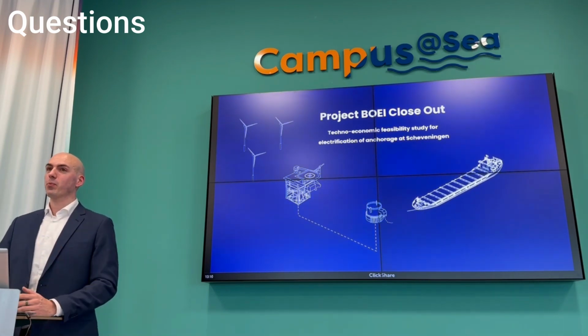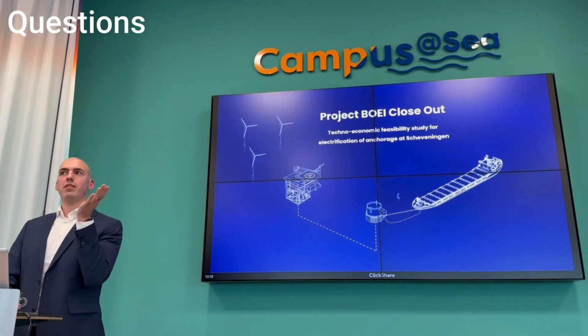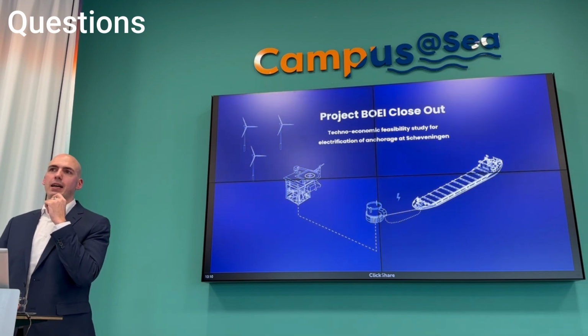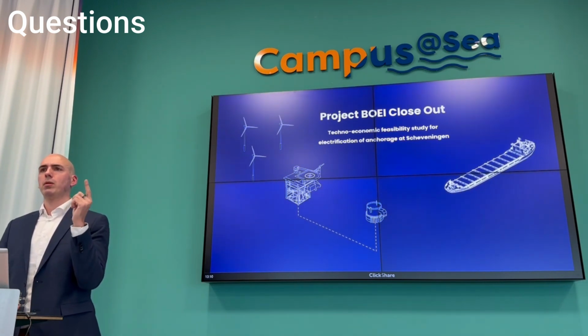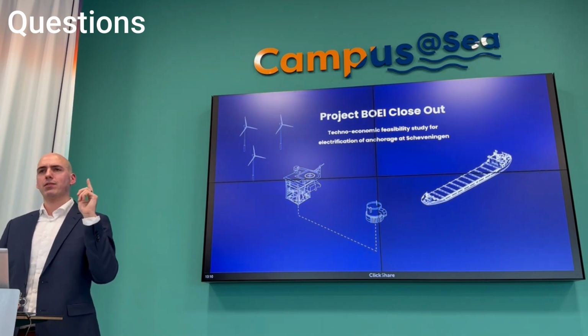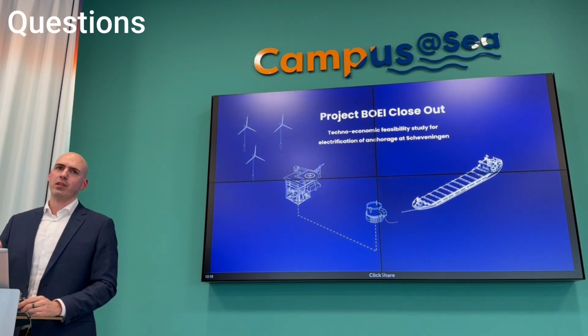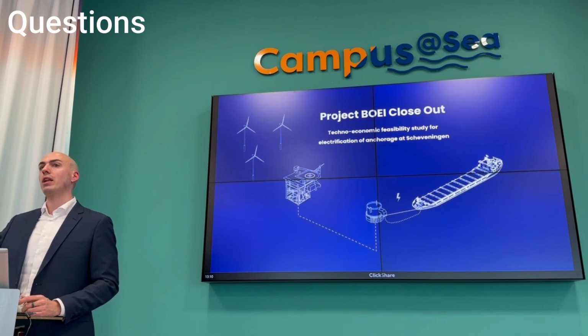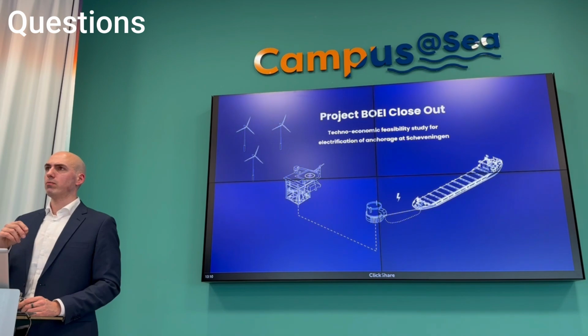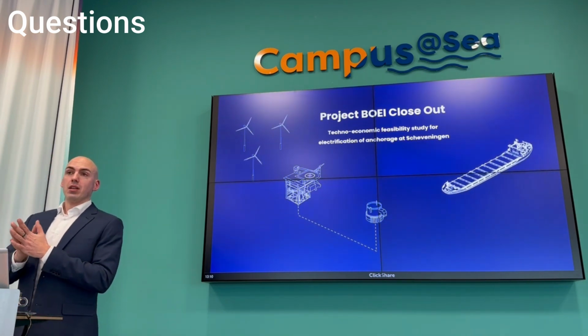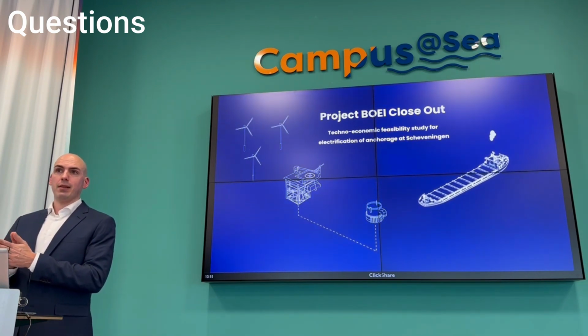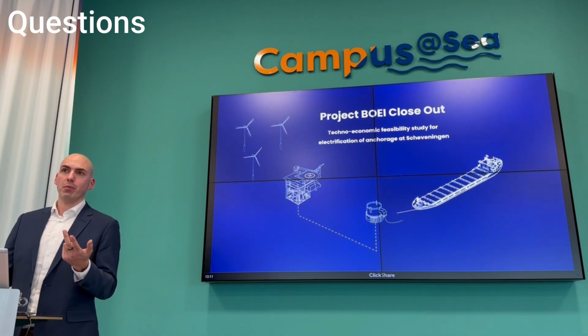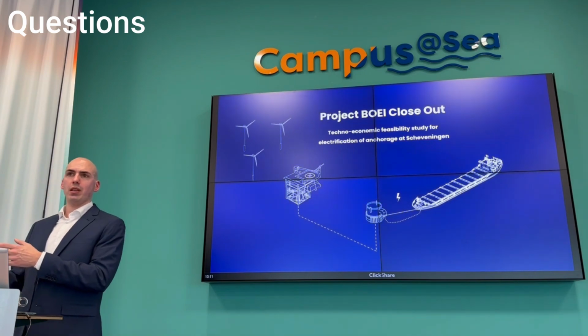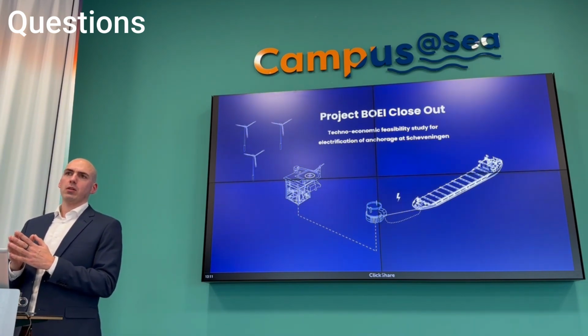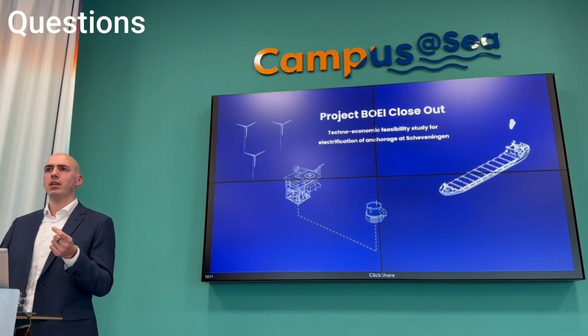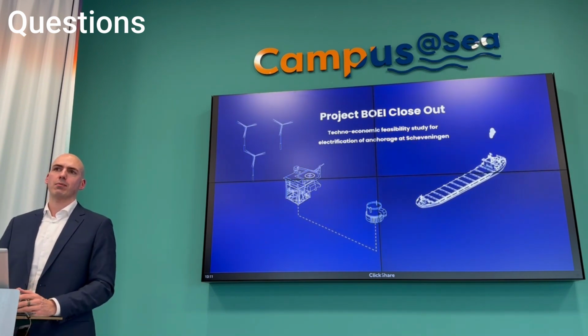Maybe, I was just telling that to Anouk. If I had, let's say, 50 million, I'd maybe personally go for a new land cable, because even though that might take longer, you're not dependent on Q13. I'd especially consider that if you want to add 10 vessels more long term. That would be a better solution, unless Q13 isn't decommissioned, which is being planned for the end of this decade. That's also one reason I'd favor a new cable. But if it's not decommissioned, or somebody else buys Q13, that would absolutely be the preference. So put differently, you need a different owner committed for at least 15 years, or a land cable. From a commercial aspect, that would be the case.